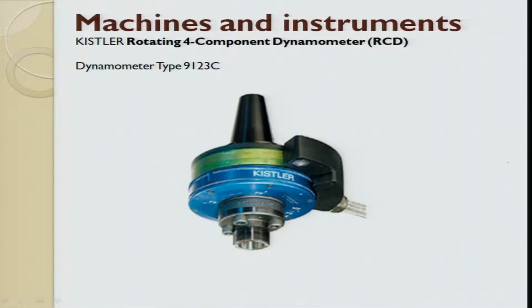Now this is a rotary dynamometer. This is another version of this Kistler dynamometer, right? And this is used for our drilling and milling experiments. It is a 4 component dynamometer, and it can measure 4 different components: Fx, Fy, Fz, and moment also. F in X, F in Y, F in Z direction, and also moment in Z direction, right?